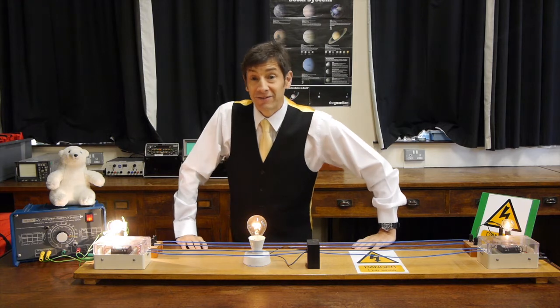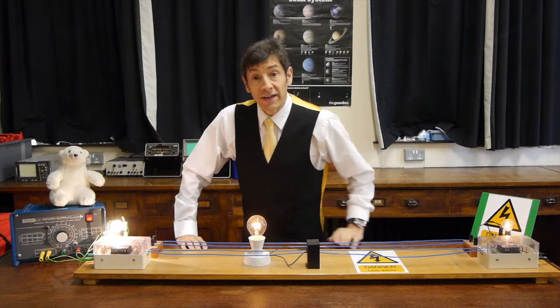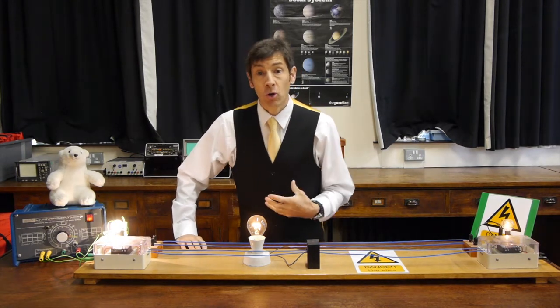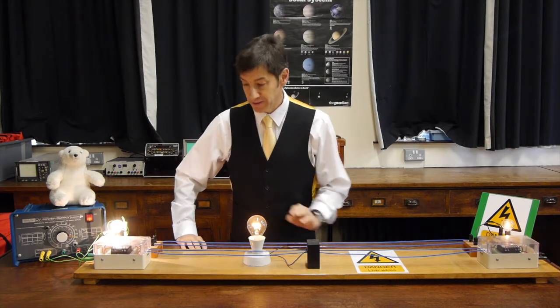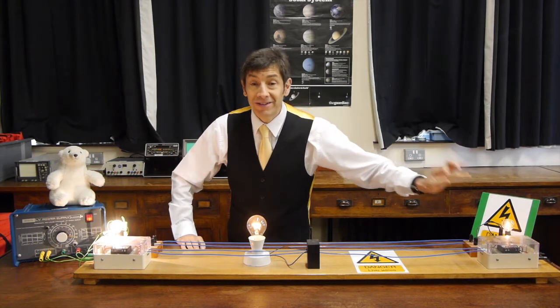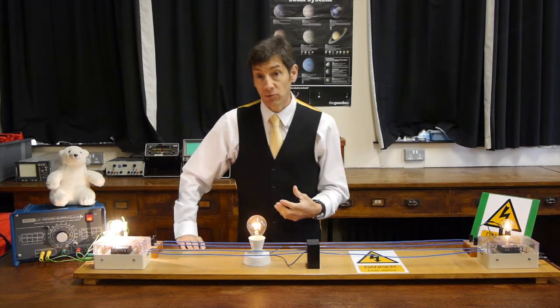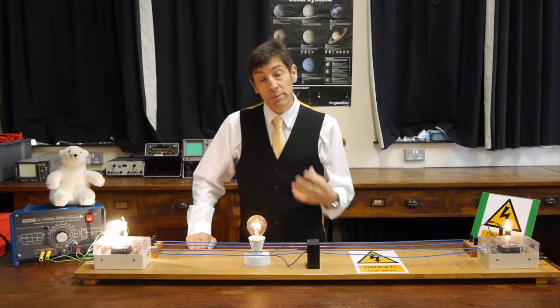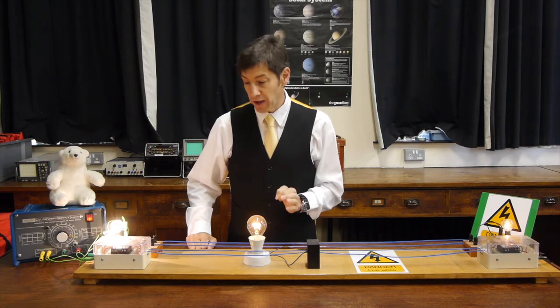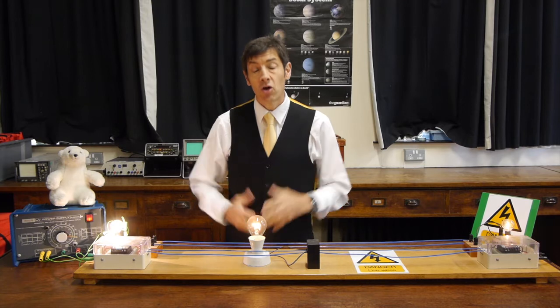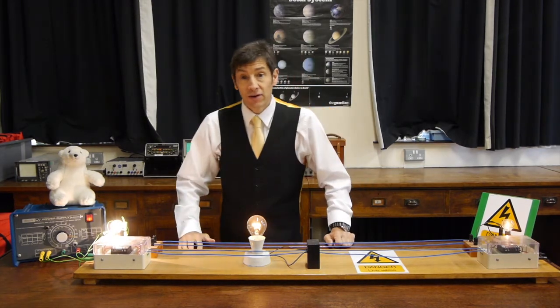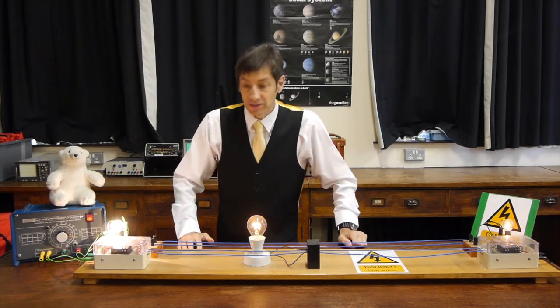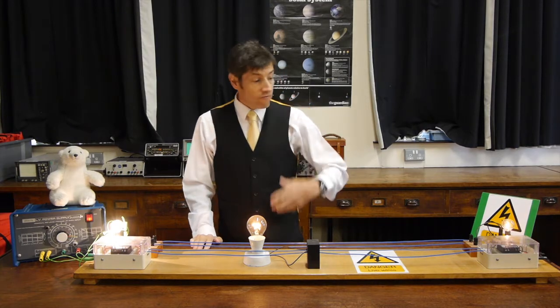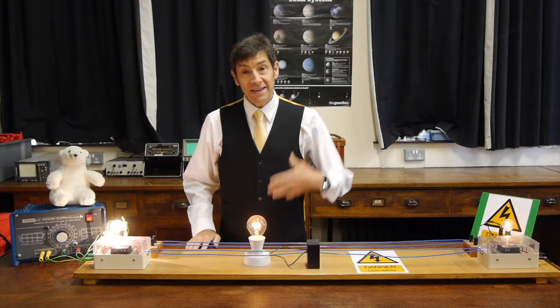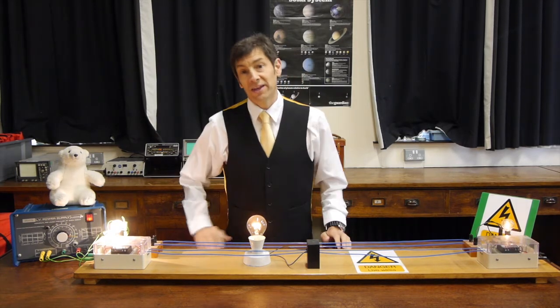There's something else going on that's really clever. The heating effect on the cables depends not on the current, but on the current squared. Have a think about that: if more buildings are taking electricity and the current in the cables doubles because they're drawing twice as much power, the losses in the cable will be proportional to that current squared. So twice the current means 4 times the power loss in the cables - they'll get really warm and we won't get much electrical energy at the far end. Now imagine drawing 4 times as much current: 4 squared is 16, so you'd lose huge amounts of energy in the cables.